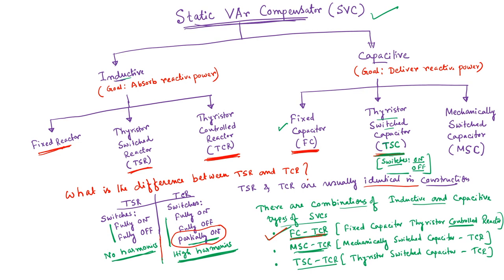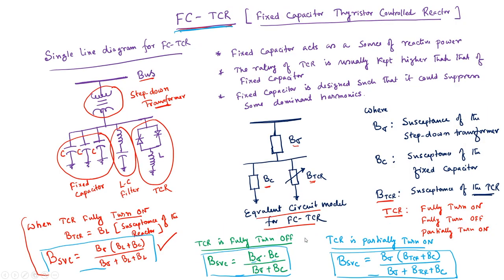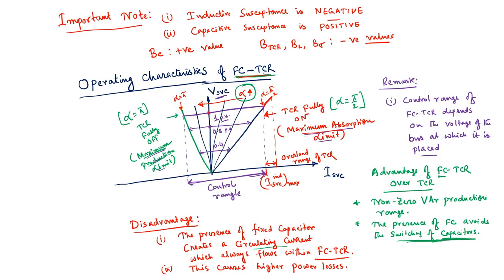The advantage of FC-TCR over normal TCR is that since we have a fixed capacitor bank, we have the flexibility of both reactive power delivery and reactive power consumption. The VI characteristics of fixed capacitor TCR have a non-zero production limit, whereas normal TCR had a zero production limit. But the disadvantage of having this fixed capacitor is that there will be a circulating current which will always flow between the fixed capacitor and the TCR when they are operating, resulting in additional losses.